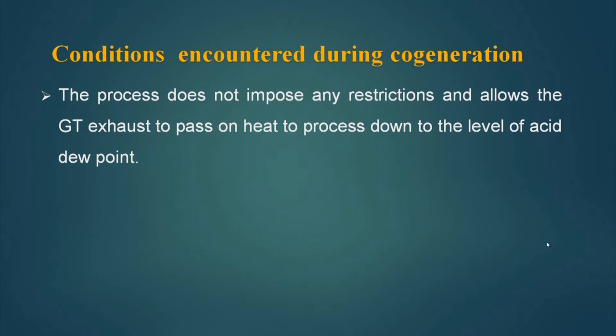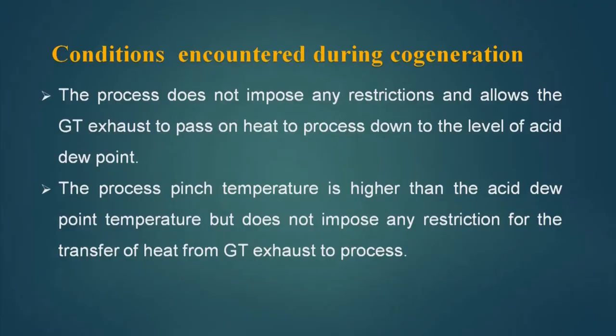Let us analyze the conditions encountered during cogeneration. The first point: the process does not impose any restriction and allows the GT exhaust to pass heat to the process down to the level of the acid dew point. If it is not imposing any restriction, this is a free problem and easier to tackle. The second situation may be that the process pinch temperature is higher than the acid dew point temperature but does not impose any restriction for the transfer of heat from GT exhaust to process. We have seen how to tackle this — we can use the recuperator to bring it down so it crosses the acid dew point.